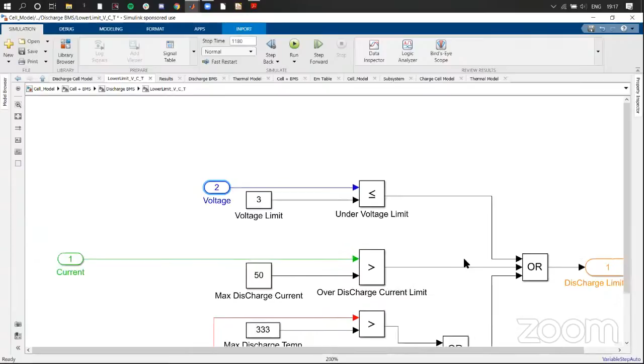You can see we've set a max current and max discharge current limit, a max temperature, and a minimum discharge temperature. Discharge can happen at lower or higher temperatures, so we define a logic inside the BMS to stop it if the temperature reaches certain limits, considering both the ambient temperature and the cell's internal temperature.